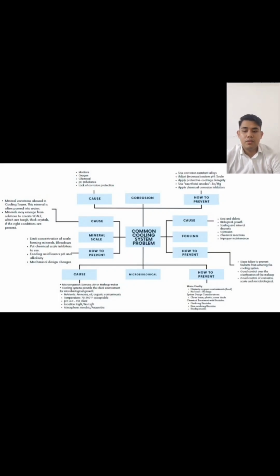The third mind map is common cooling system problems. We have 4 common cooling system problems. The first one is corrosion, second is mineral scale, third is microbiological, and last is fouling. Corrosion will occur in our system because of moisture, oxygen, chemicals, pH imbalance, and lack of corrosion protection. And how to prevent it? The first is to use corrosion resistant alloys. Second, adjust the system pH. Third, apply protective coating. Fourth, apply chemical corrosion inhibitors.